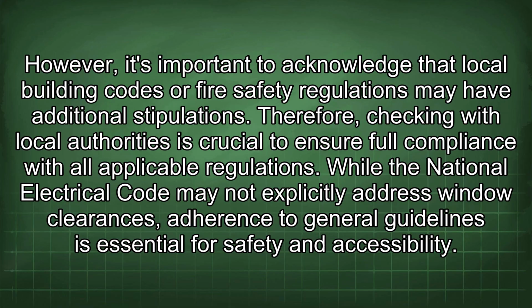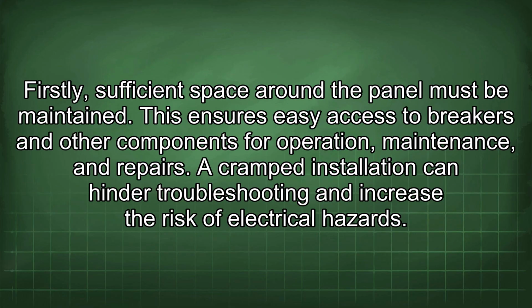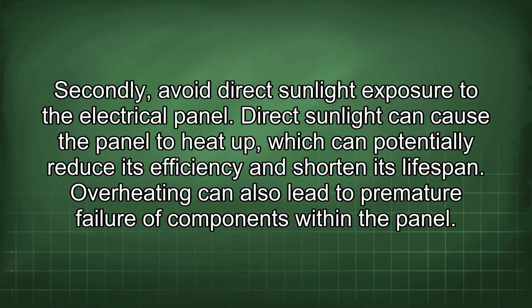While the National Electrical Code may not explicitly address window clearances, adherence to general guidelines is essential for safety and accessibility. Firstly, sufficient space around the panel must be maintained. This ensures easy access to breakers and other components for operation, maintenance, and repairs. A cramped installation can hinder troubleshooting and increase the risk of electrical hazards. Secondly, avoid direct sunlight exposure to the electrical panel. Direct sunlight can cause the panel to heat up, which can potentially reduce its efficiency and shorten its lifespan. Overheating can also lead to premature failure of components within the panel.